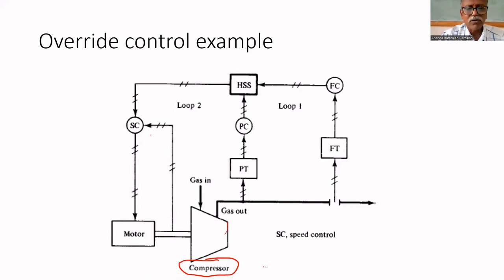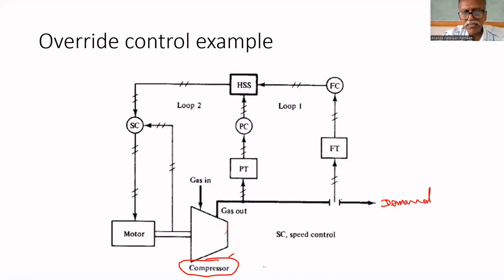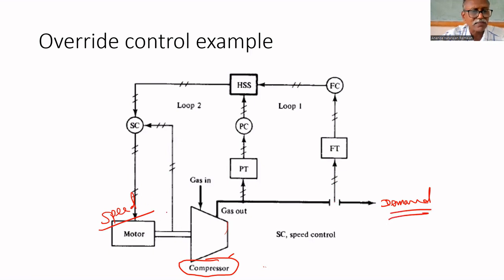Another example for override control is a compressor. The compressor will supply pneumatic signal to many processes. For that, a flow controller is there. Depending upon the demand, the flow transmitter will adjust the speed of the motor. To maintain the flow rate, it will adjust the motor. If the demand increases, the flow rate will decrease, so the motor speed has to be increased.